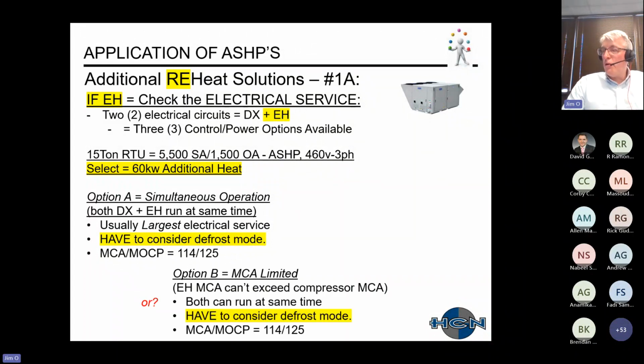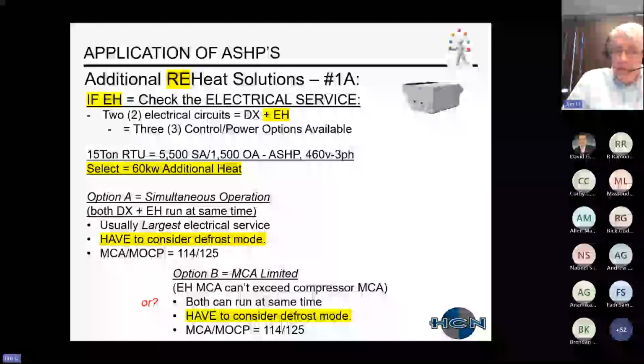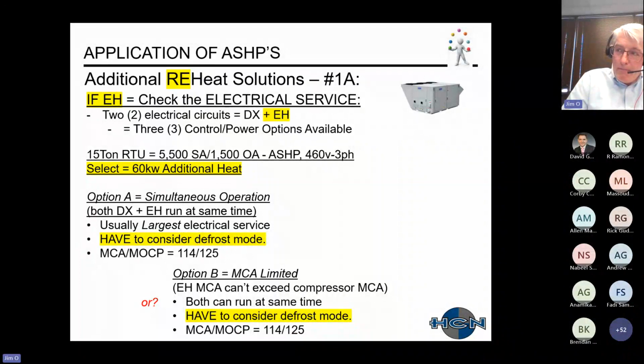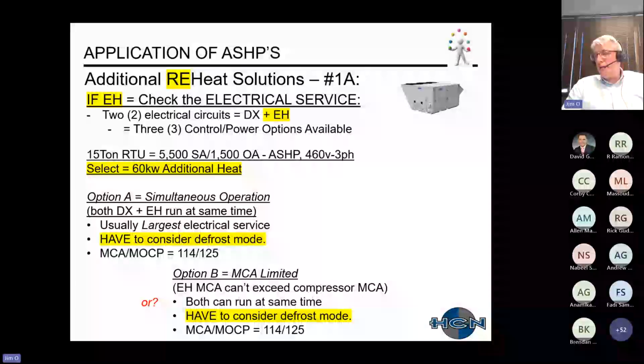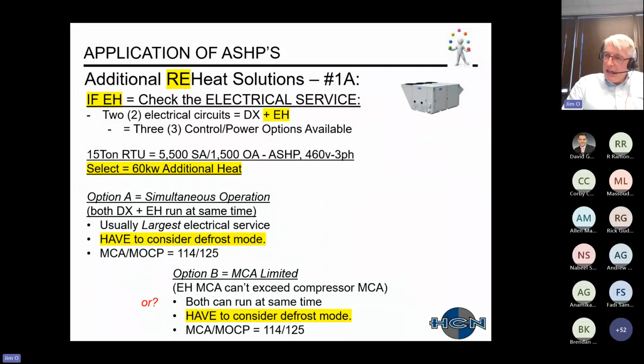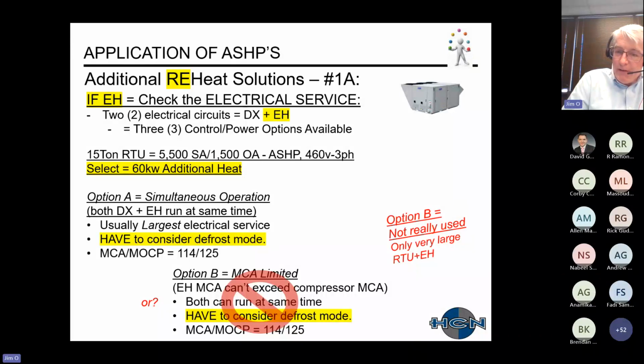Option B, I'm not sure if all manufacturers have this one available, but you can select a maximum MCA of your electric heater that your unit will not exceed. Maybe you have an existing unit with a certain MCA, and you don't want to go over the existing MCA, because you'd have to pull new wires from your circuit breaker out to the unit. They both can run at the same time. You do have to consider defrost mode. This example here is probably a bad example, but my MCA was the same as that. And I will say that option B is not really ever selected.